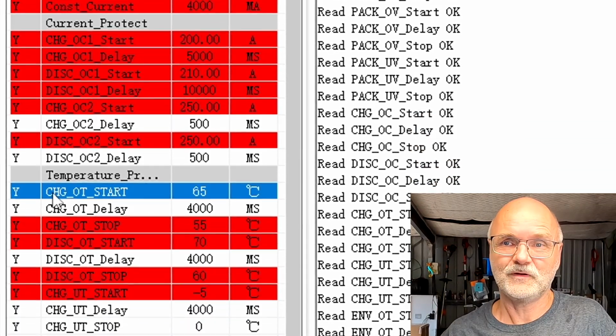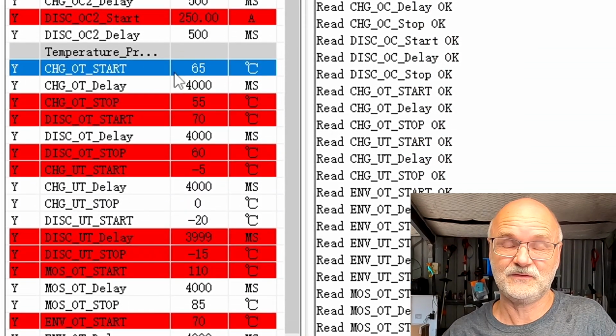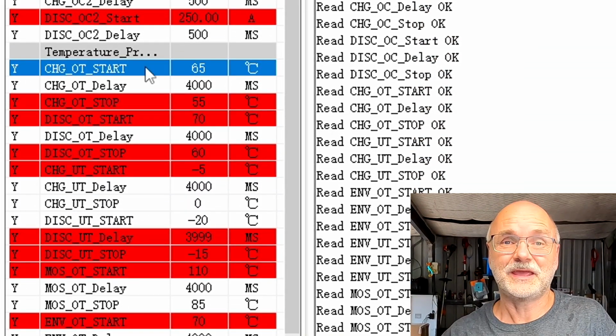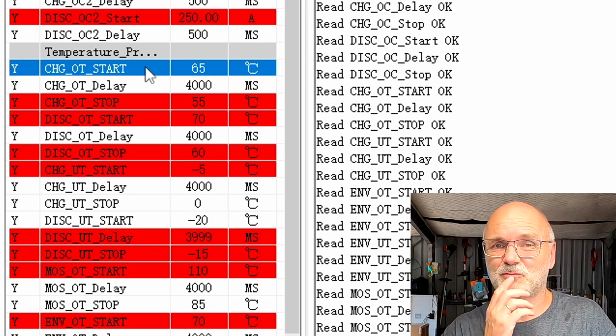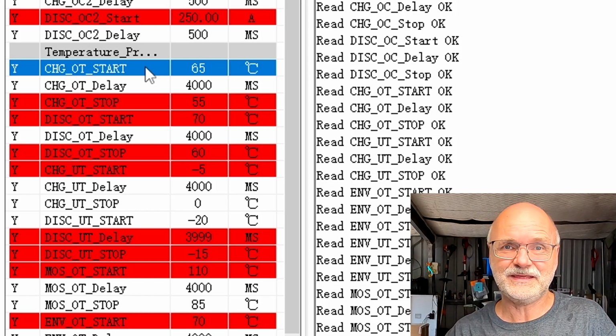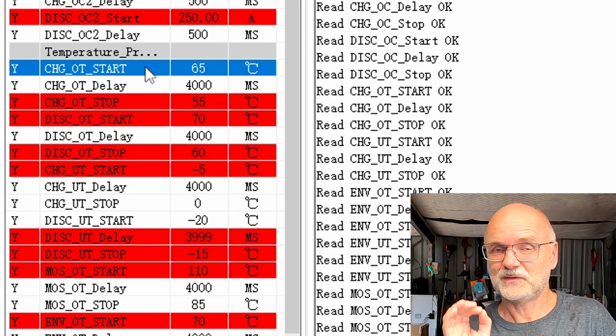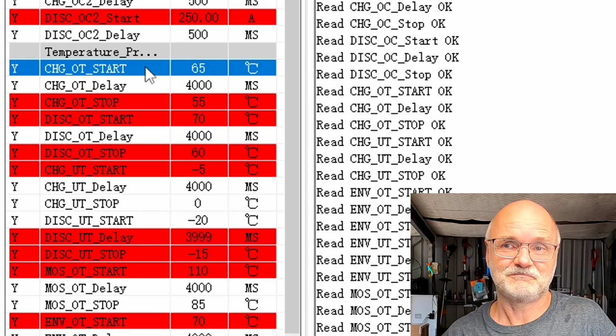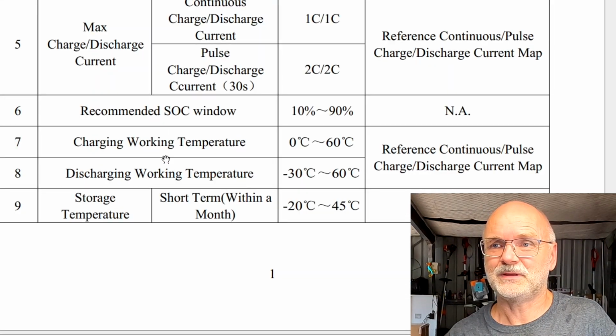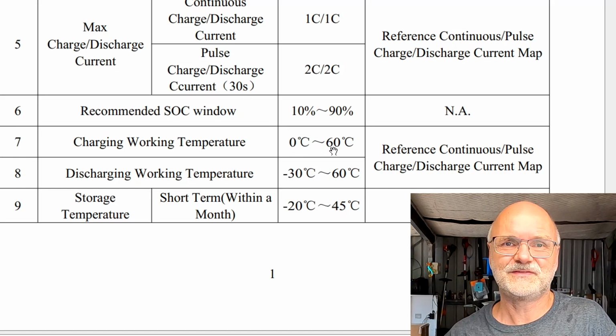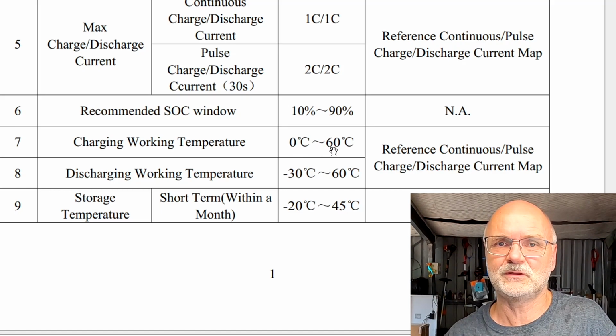And the charge over temperature disconnect sits on 65 degrees. At the beginning, I thought, well, 65 degrees is a bit too high for these battery cells. And I had a look at the EVE LF230 specification sheet, and I was right. Pulling this one up, it says charging working temperature 0 to 60 degrees. So up to 60 degrees we can charge the battery, which is totally insane. And discharging as well, 60 degrees.